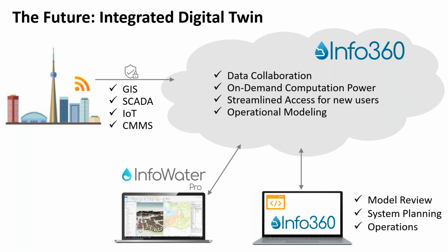If you have full hourly AMI data, you could get an hourly time series of non-revenue water, and if that suddenly grows or jumps, that's a really strong indicator of a pipe burst or leakage getting worse in your system. So that's an exciting capability, open for APIs and so on.